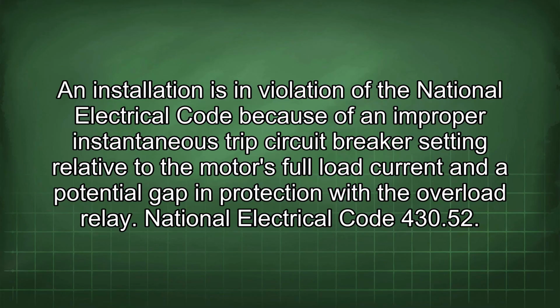An installation is in violation of the National Electrical Code because of an improper instantaneous trip circuit breaker setting relative to the motor's full load current and a potential gap in protection with the overload relay. National Electrical Code.